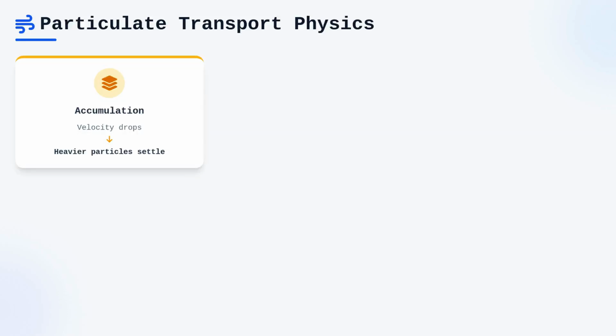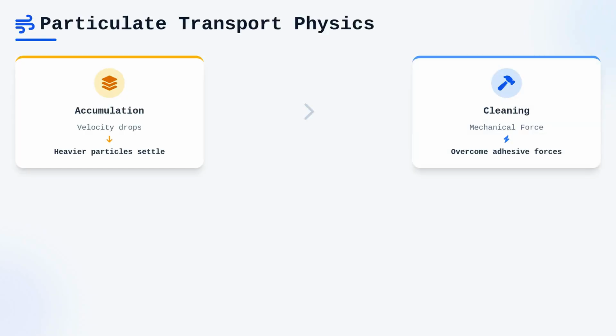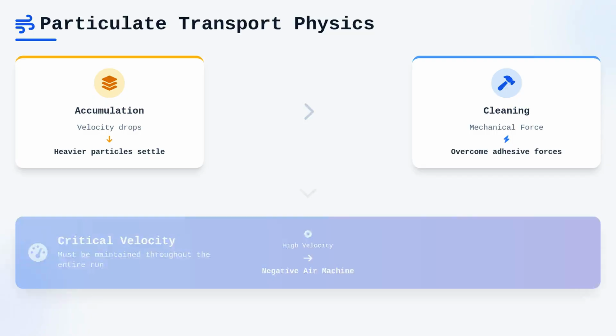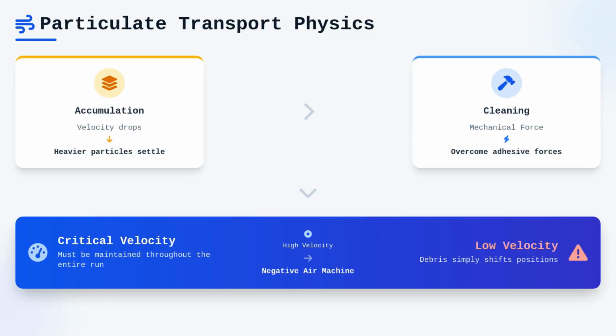Particulate transport, or the physics of how dust and contaminants move through airstreams, relies heavily on the velocity of the air. Heavier particles settle out of the airstream when the air velocity drops below a certain point, creating the accumulation patterns you will encounter on inspection. When we initiate cleaning, our goal is to overcome the adhesive forces holding these particles to the duct wall, often using mechanical force to reintroduce them into the airstream for capture. Transporting these particles safely to our negative air machines requires maintaining enough velocity throughout the entire length of the duct runs. If the velocity drops too low in the branch ducts, you will find that your heavy debris simply moves from one spot to another rather than exiting the system entirely.